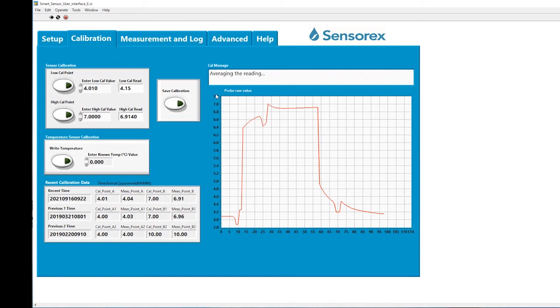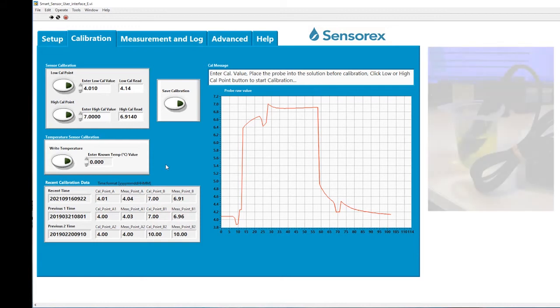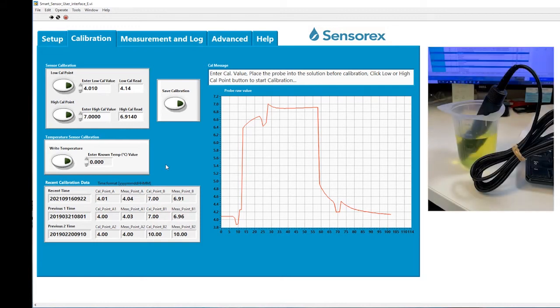Let's monitor the calibration message here. The first thing it's going to do is tell you it's averaging the reading, and now it finished the calibration, and it's prompting you to place the probe in the next solution. In this case, it's going to be pH 7. So first I'll rinse the probe in deionized water, move the probe now to pH 7, and we'll repeat the same process on the high calibration point here.